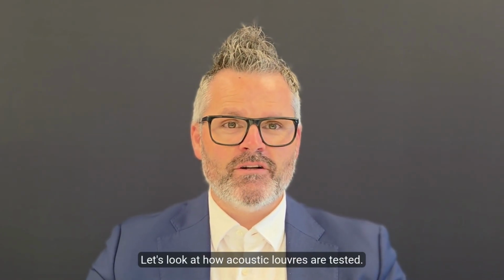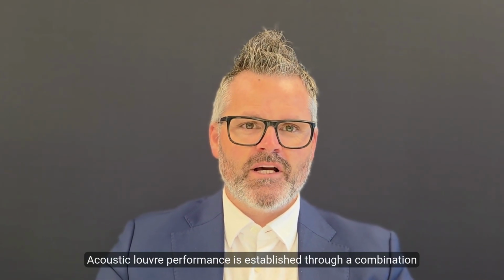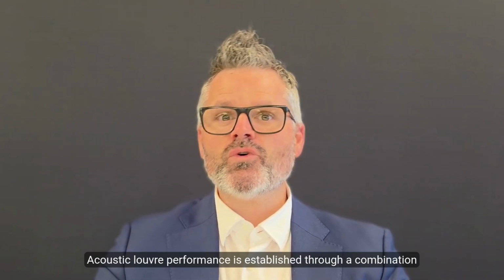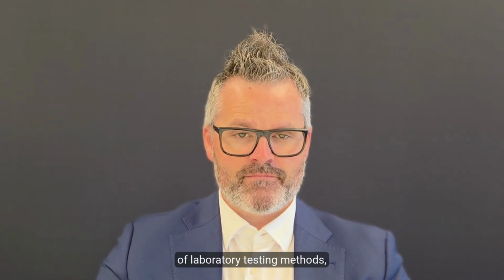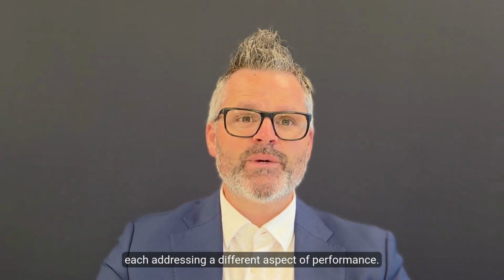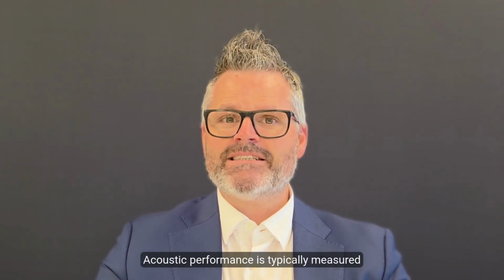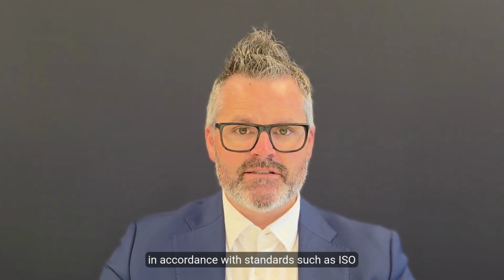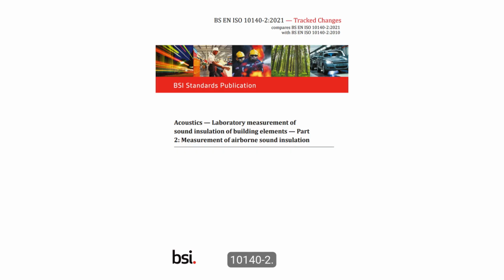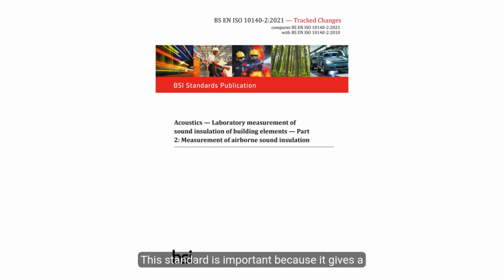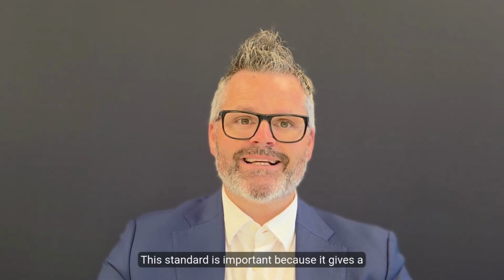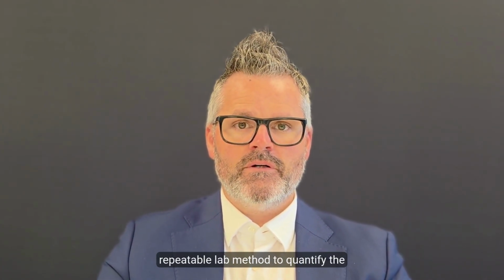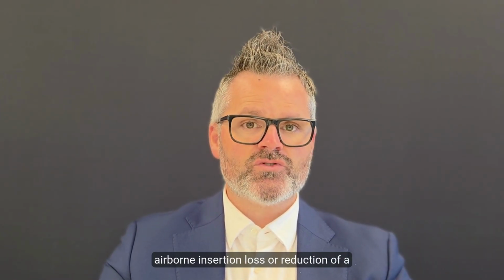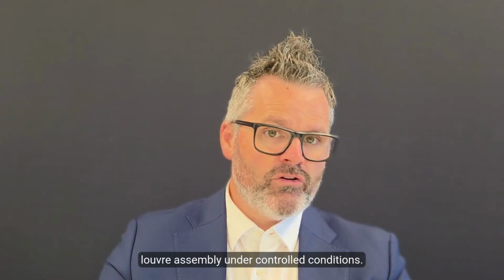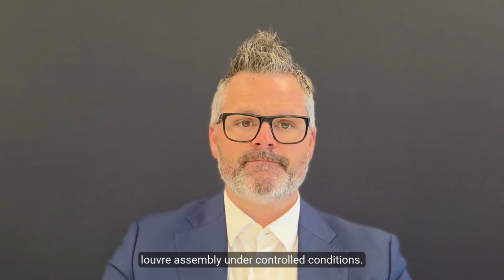Let's look at how acoustic louvers are tested. Acoustic louver performance is established through a combination of laboratory testing methods, each addressing a different aspect of performance. Acoustic performance is typically measured in accordance with standards such as ISO 10140-2. This standard is important because it gives a repeatable lab method to quantify the airborne insertion loss or reduction of a louver assembly under controlled conditions.